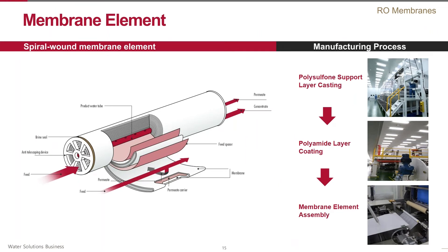The most widely used membrane module configuration today is a spiral wound element, as shown here. It consists of a number of so-called envelopes. Each envelope is basically two membrane sheets separated by a thin plastic net called a permeate spacer — a permeate tricot that forms a channel allowing transport of the permeate towards the permeate tube collector.